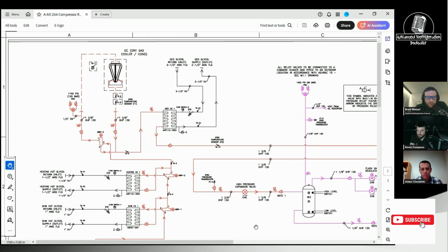So you'll have to excuse me because I'm trying to envision this. So you guys are doing straight industrial systems that are 90 bar, where you're basically dumping hot gas into the suction of the coil and letting it go back to a discrete header, right? Do you guys have a lower pressure, almost like a cool gas, where you're getting that vapor off the flash tank, or does Zero Zone not do that typically? We do not do that.